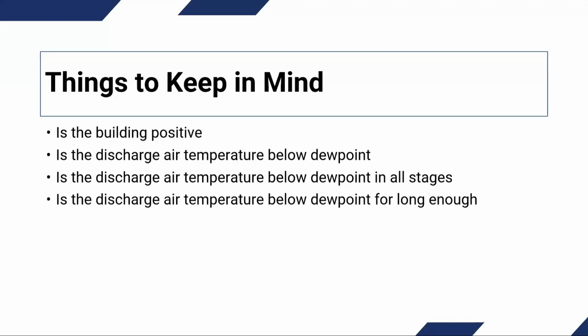Another key factor is the discharge temperature at dew point for long enough. So the very first job that I ever did by myself here, units we just changed code to where we had to increase the outside air. I was nervous because it was my first project. I had to make sure that everything was right, and I did. And we had all kinds of humidity problems in the project.